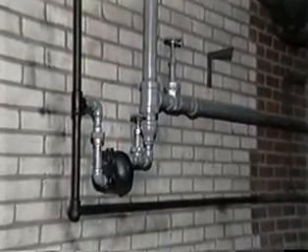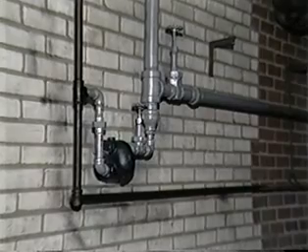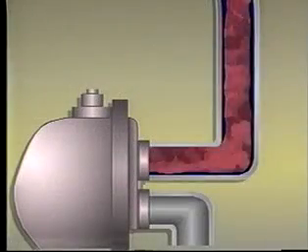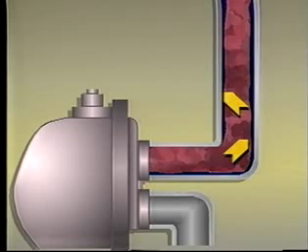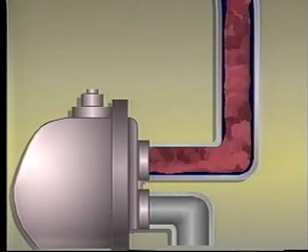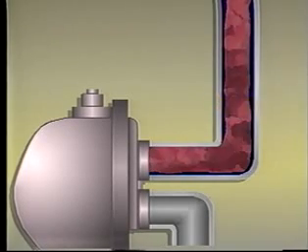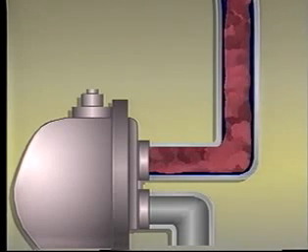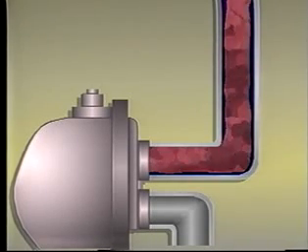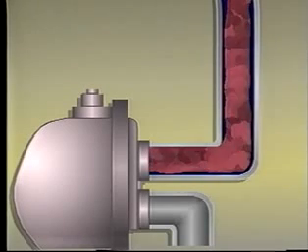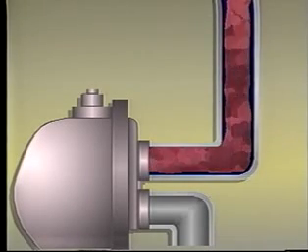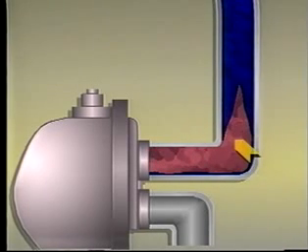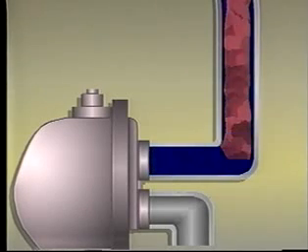Differential shock can also become a problem when elevated heat exchange equipment is drained with a substantial vertical drop ahead of the trap. Under normal conditions, condensate drains down the walls of the pipe. A sufficient volume of steam constantly flows down the center of the pipe to replace the steam that is condensed by radiation losses of the piping and the trap body itself. The steam flow rate increases if a thermostatic element such as the bellows or wafer in an F and T trap opens. If a slug of condensate seals off the pipe, steam collapses downstream of the seal. Again, a pressure differential forms, and this, along with gravity, accelerates the slug.